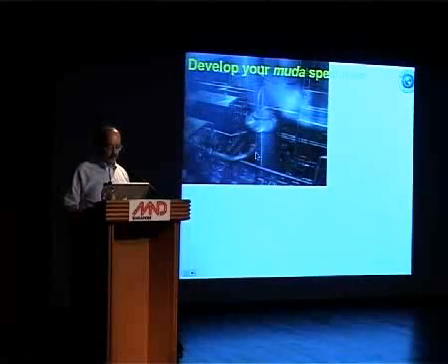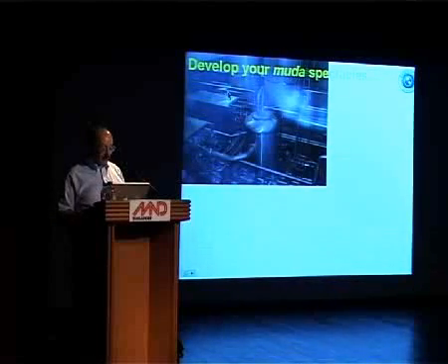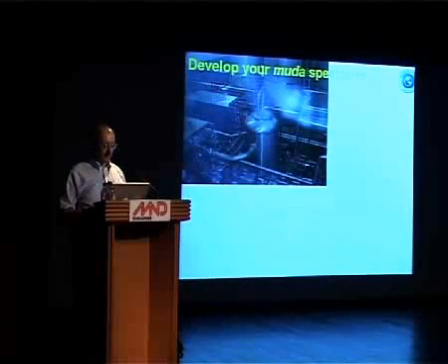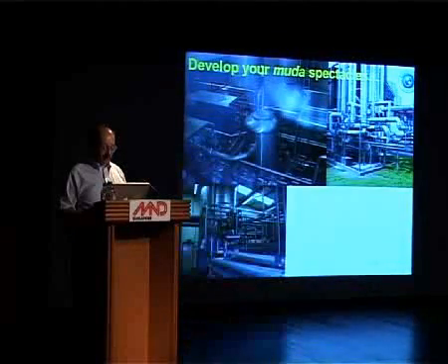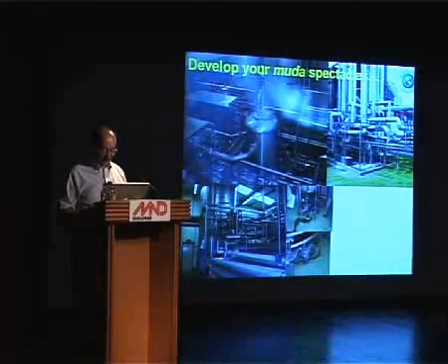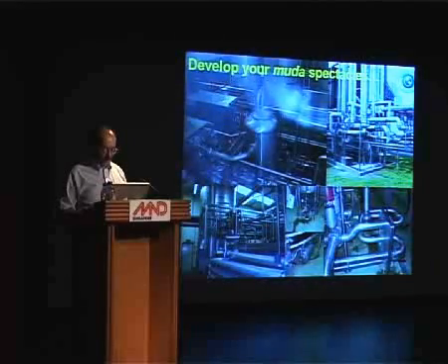After a while, you develop special muda spectacles. Take a look at this little tank back here and what happens to its pipe run. I figured if that tank had been rotated 30 degrees around its vertical axis, we could have eliminated 11 bends. When you start taking a careful look at process piping layout, it's obvious that whoever designed this stuff was thinking about something else. And perhaps they were paid by the bend.